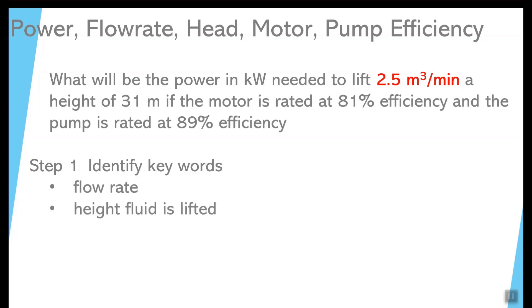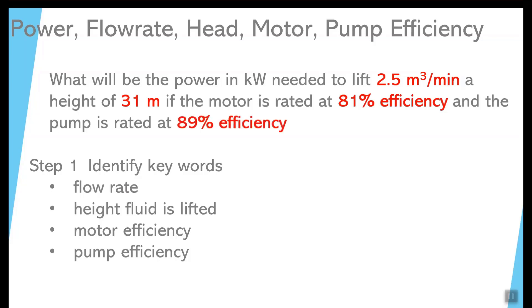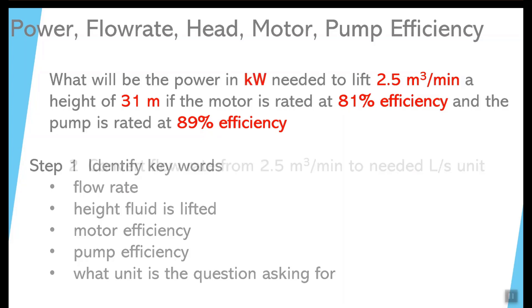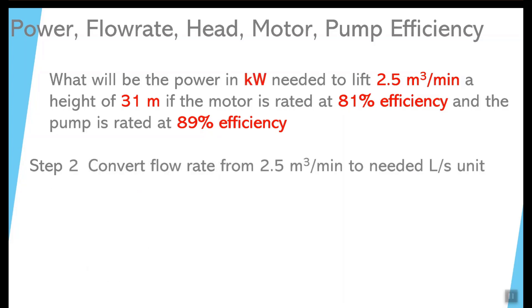The second keyword is how high you have to lift the water — in this case, 31 meters. Third, the motor efficiency is 81% and the pump efficiency is 89%, or 0.89. Plug those numbers into the formula. The unit the question is asking for is kilowatts.